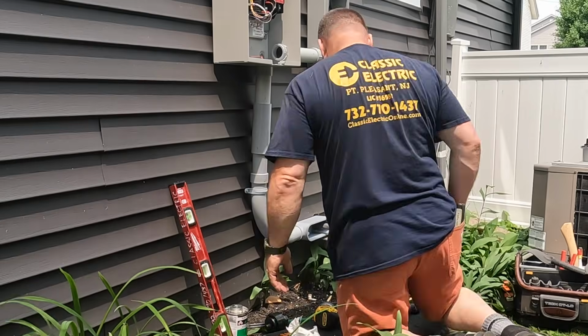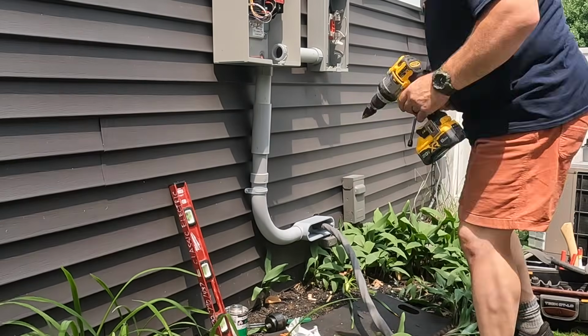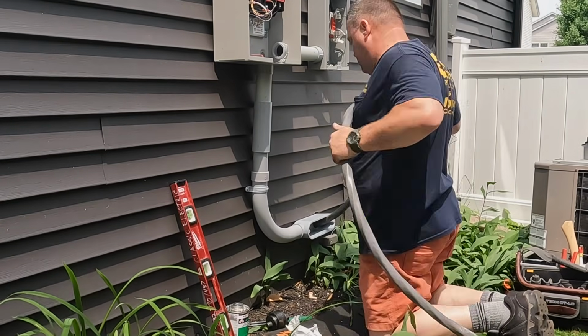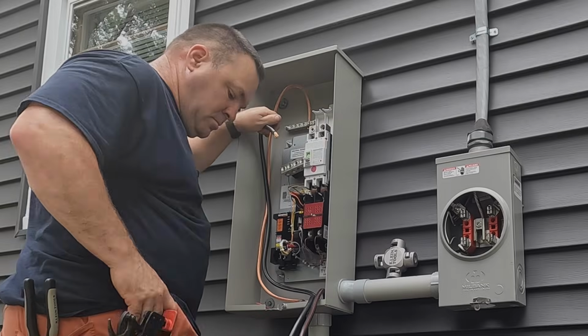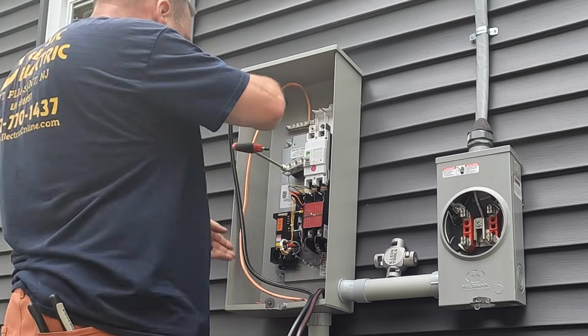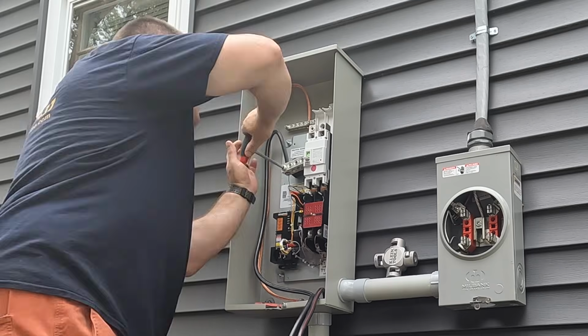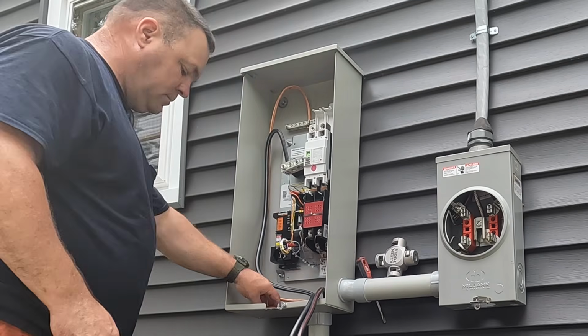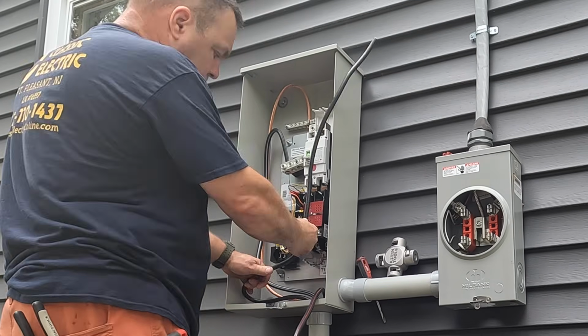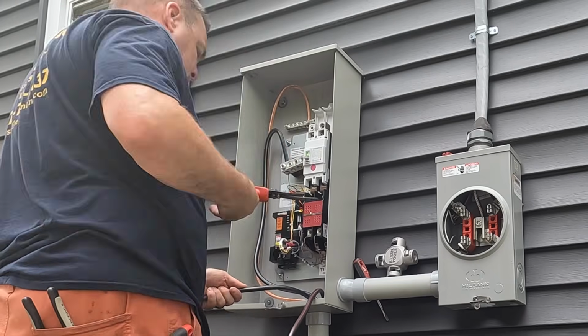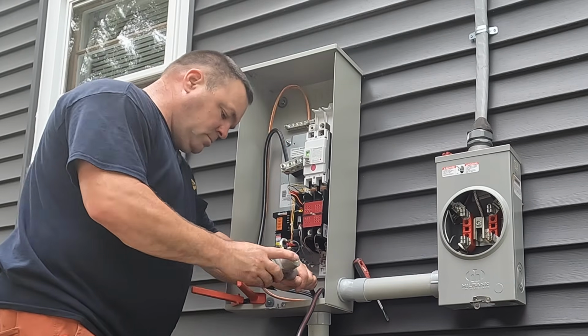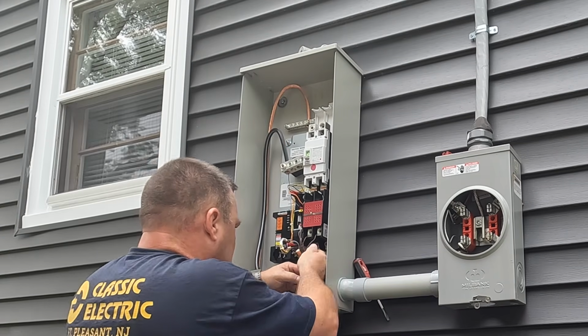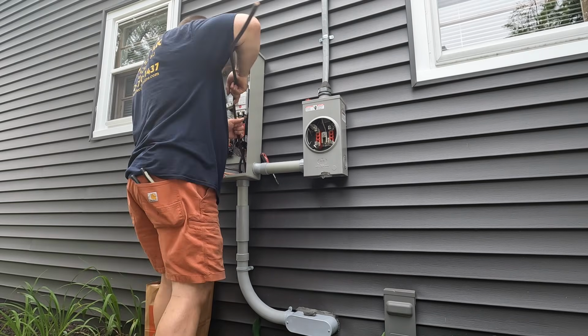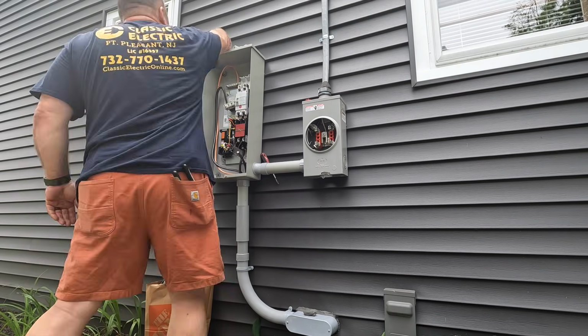The expansion coupling is required where 2 points are fixed. So should that conduit get heated or hot and expand, the expansion coupling will help that along. And so the new main disconnect for this property is here in this transfer switch, which is why we're running a 4-wire between the transfer switch and the load in the basement, or rather the customer load, we'll call it. And so here I'm just terminating my conductors from the load.